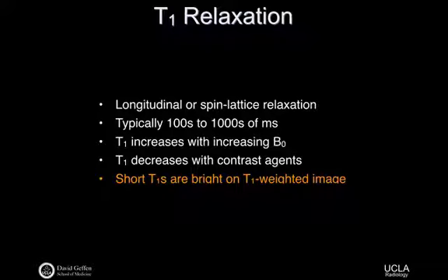So if you go to a higher field, then your T1s actually lengthen a little bit. And that means, again, if you have a protocol at 1.5T, that's not going to work identically at 3T. That's at least another reason.